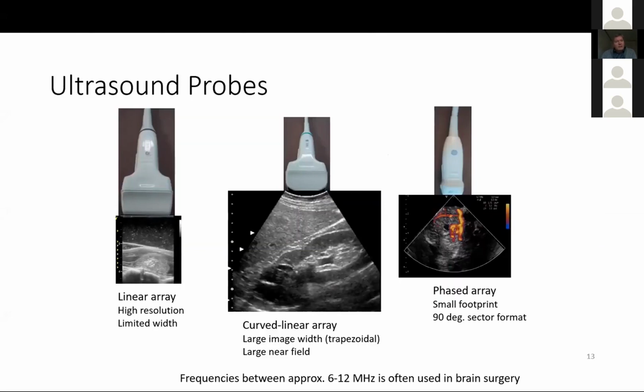And there are different ultrasound probes that you can use. You have the flat linear array. Here it is imaging a spinal tumor. And the linear arrays usually have a high resolution, but the width of the image is limited by the width of the transducer.